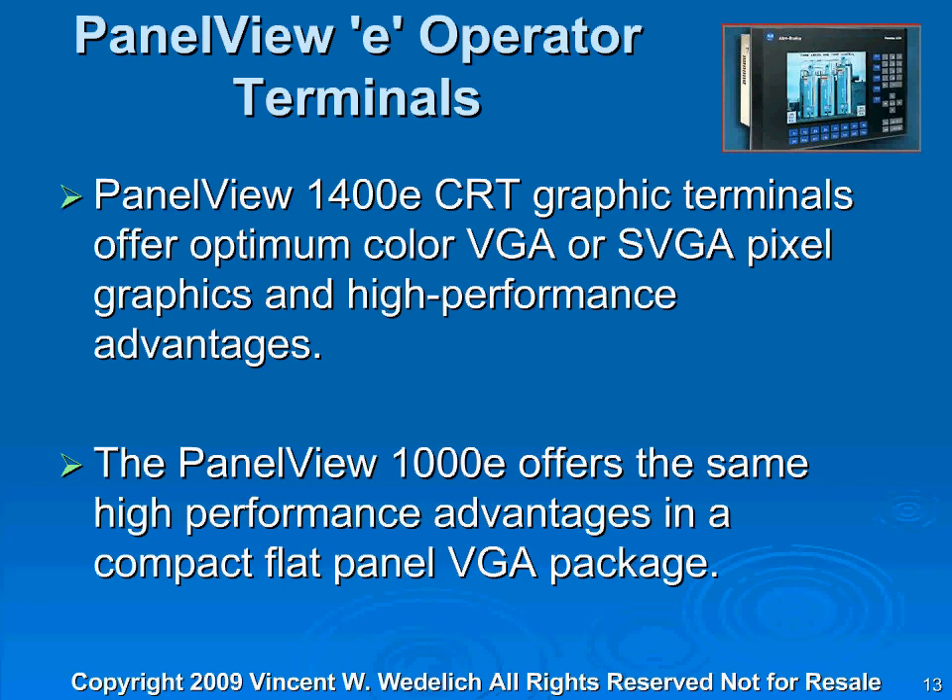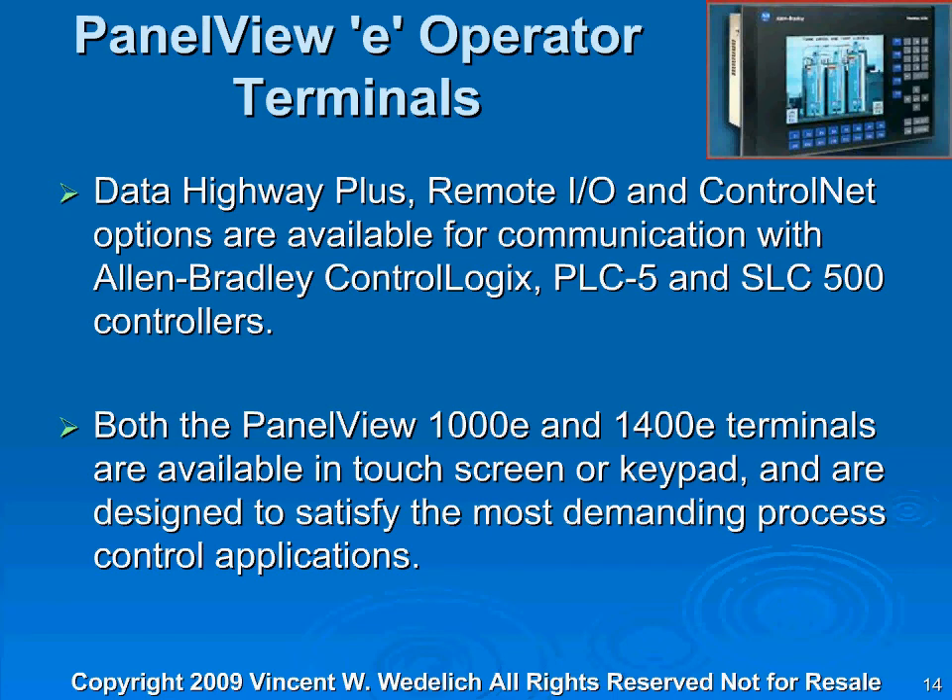The only drawback is if it fails or breaks, they're hard to get a hold of, and I don't even know if they make these anymore. With the PanelView E Operators, you get all these modules that you can snap in — communication modules — so it's not a problem. You get Highway Plus, Remote I/O, and ControlNet options. These are all available communications with Allen-Bradley ControlLogix, PLC5, and SLC 500 controllers. Both the PanelView 1000E and 1400E terminals are available in touchscreen or keypad versions.